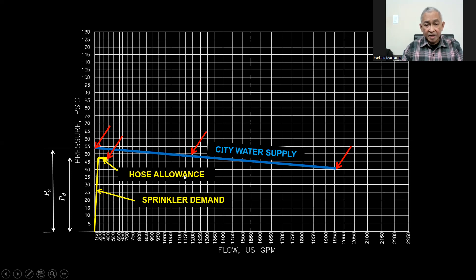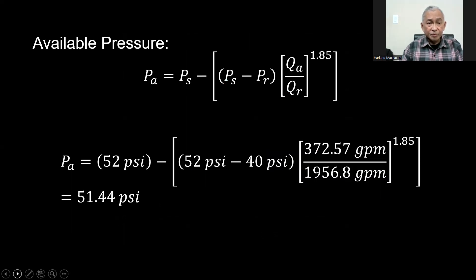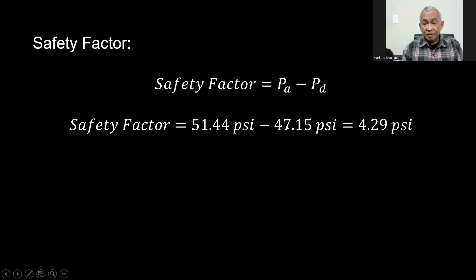We now have the city water supply plotted, and our task is to compute the safety factor. We know the city water supply is sufficient to cover the hose and sprinkler requirements. The next step is to compute the available pressure of the city water at a sprinkler demand of 372.57 GPM. The result using this equation is 51.44 PSI. Subtracting the sprinkler requirement of 47.15 from 51.44, we get a safety factor of 4.29 PSI.